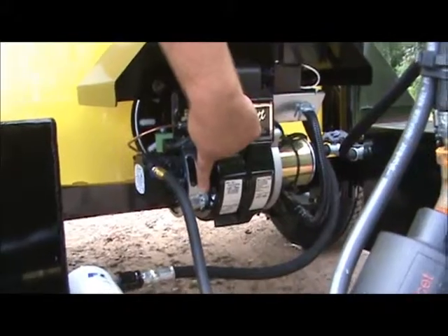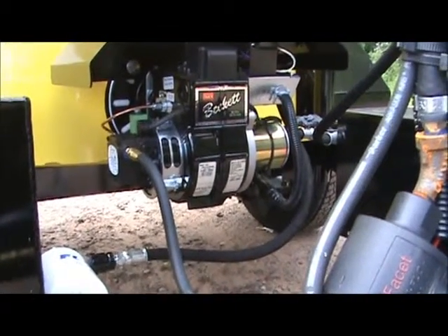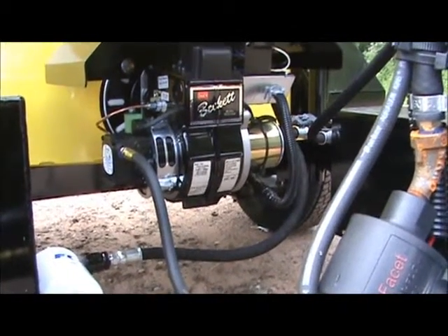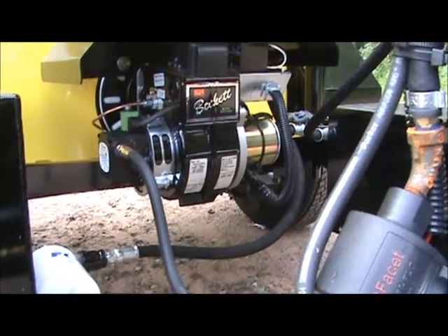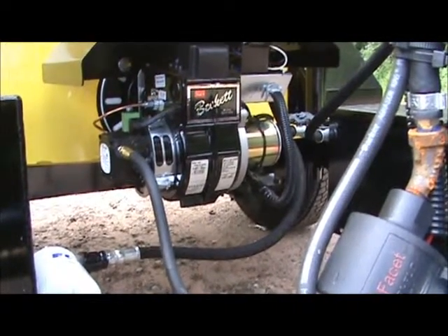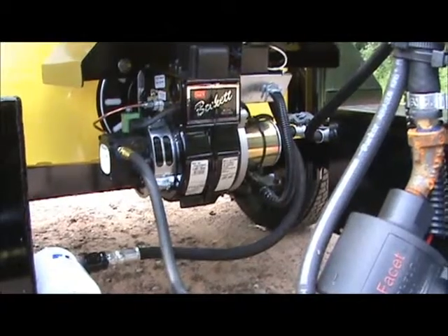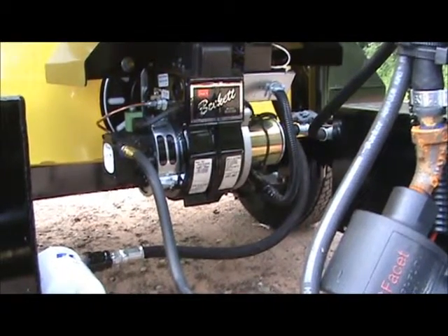The screw here in this band is our large air adjustment. So we'll loosen that screw and adjust that up. Now, if you're noticing that your burner is smoking, you're getting a lot of black smoke out of it, it's because it's got more fuel than it's got air, so we've got to give it a little bit more air.